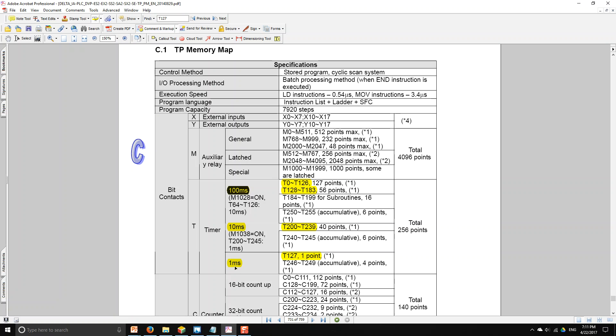Timer T127 works every one millisecond, so increments are every one millisecond. There are also special memories you can activate to change the scale. For instance, if you activate M1028, timers T64 through T126 will change from working every 100 milliseconds to every 10 milliseconds.